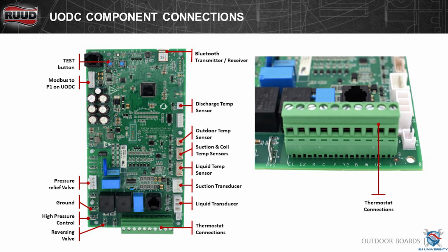Once again, your thermostat connection's there. On this mid-tier universal outdoor control board, even though it does have the Y2, B, and W, I'll get to U1 and U2 in a minute. Even though it has those connectors, I'm being told, and I have not been able to try this yet, those are dead on the board. Okay? The only thing that is good is E1, E2, R, and C on this board. Why it's there and you can't use it, I don't know. I haven't had a chance to get down to our lab and try it yet.